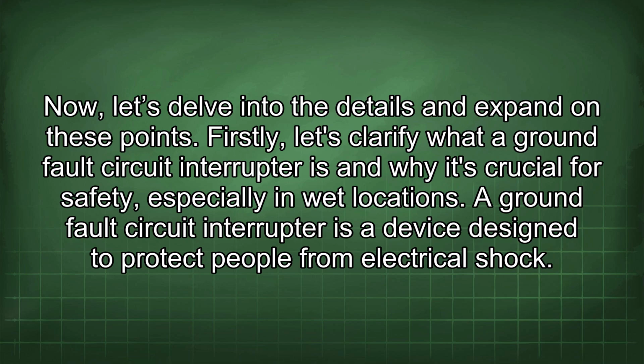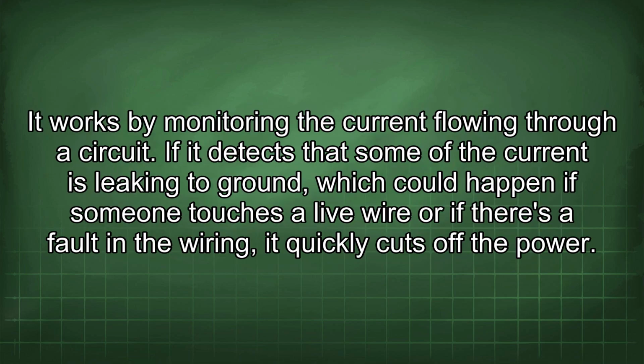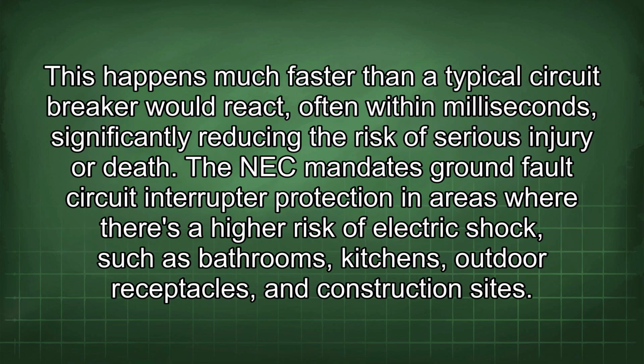A ground fault circuit interrupter is a device designed to protect people from electrical shock. It works by monitoring the current flowing through a circuit. If it detects that some of the current is leaking to ground, which could happen if someone touches a live wire or if there's a fault in the wiring, it quickly cuts off the power.